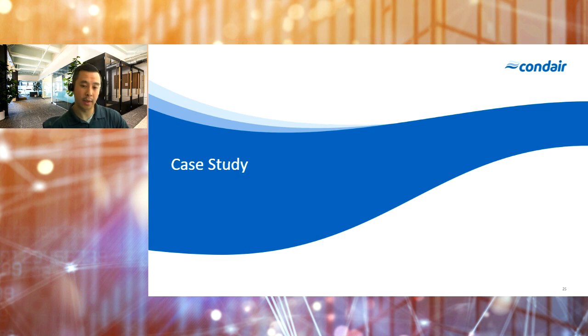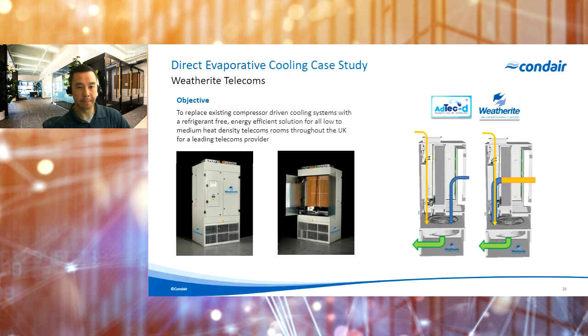What I want to end here with is just a case study. This is a case study for a UK-based AHU manufacturer called Weatherite. The objective here was to replace existing 30 kilowatt compressor-driven cooling systems with a refrigerant-free, energy-efficient solution for low to medium-sized telecoms rooms for one of the leading telecoms providers throughout the UK. Now, one of the design requirements for this system was that it did need to match the footprint of the existing system, so they could be retrofitted or swapped one for one.